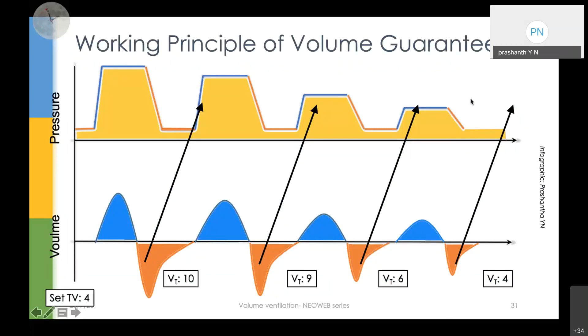So just to differentiate between control versus guarantee, a more crude method versus a more intelligent method. When you look at the tidal volumes, in both modalities it is set by the clinician. In volume controlled, I'm just telling it to push this much air into the circuit. Here also, I'm telling the ventilator this is the volume I want the lung to receive, right? In volume control, the tidal volume reaching the baby is dependent on circuit compliance. The more the circuit compliance, the less air gets into the baby's lung, and it also depends on ET leaks. But in volume guarantee, ET leak is the only thing which probably makes our work a little difficult.